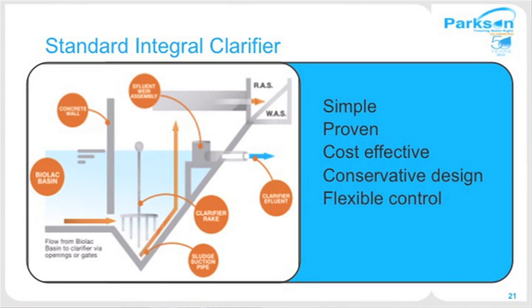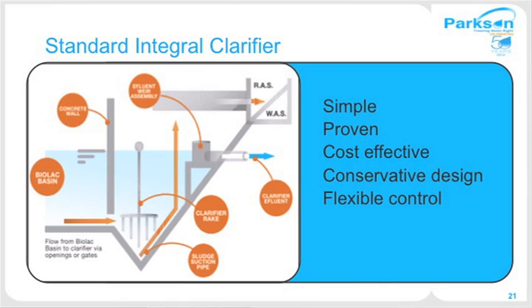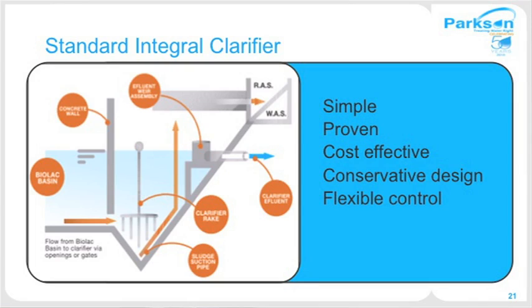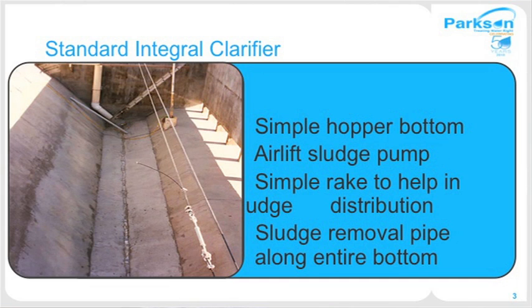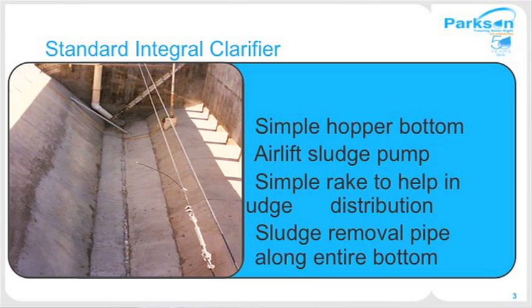Here's a closer picture of the clarifier components. One key component is the rake assembly, which moves back and forth along the length of the clarifier to keep the sludge blanket evenly distributed at the bottom, ensuring consistent sludge quality throughout the suction pipe length. At the bottom of the hopper you'll see the sludge suction pipe, grouted in with openings sized and engineered for consistent velocity throughout the pipe. The rake assembly cables and the airlift riser assembly are also shown.